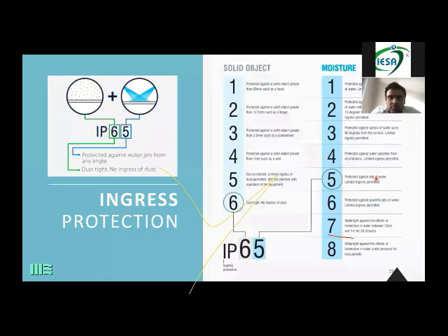But the material which is available for temporary electrification comes in IP65, certain things come in IP67. 7 basically means that it is watertight. It is watertight against the effects of immersion in water between 15 centimeters and 1 meter for 30 minutes. So there is certain material which is IP67, and certain material which is IP65. Both are right for doing your event. So the foremost thing, the panels have to be IP65 or 67. Your sockets, what you're using for temporary, have to be IP65, IP67.